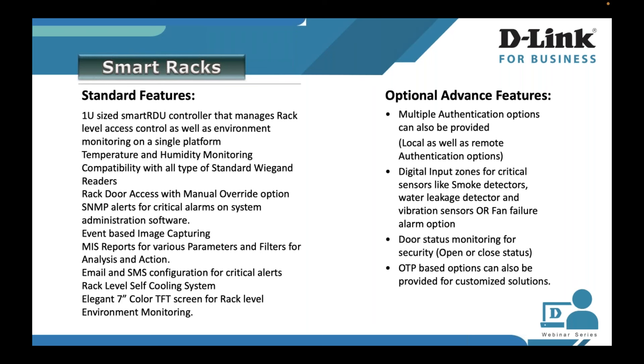Event-based image capturing, MIS reports for various parameters, filters for analysis and action, and email and SMS configuration for critical alerts are also available. The rack-level self-cooling system includes an elegant 7-inch color TFT screen for rack-level environmental monitoring where you can see the temperature inside — and the text color changes when the set threshold is crossed, raising an alert. Optional features include multiple authentication options and digital input zones for critical sensors like smoke detector, water leak detector, vibration sensors, and fan failure alarms.